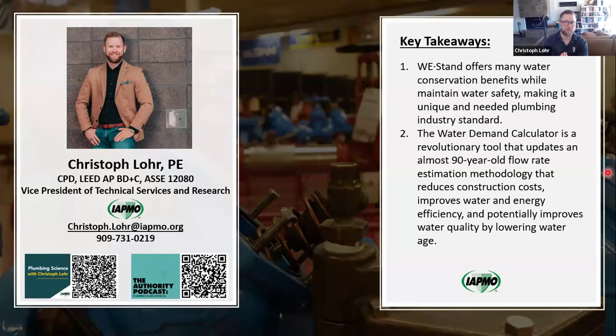I also think, from a submetering standpoint, pointing back to that IAPMO standard I discussed in terms of leak detection, that standard was IAPMO Z1349, the devices for the detection, monitoring, and control of plumbing systems. If I recall correctly, some of those devices have the ability to use sound waves in the system to determine which fixtures are on and collect that data for metering too. So some of the traditional ideas we have behind metering, that you have to have a meter into a unit and all the rest, that paradigm might be shifting, because you may not need that.